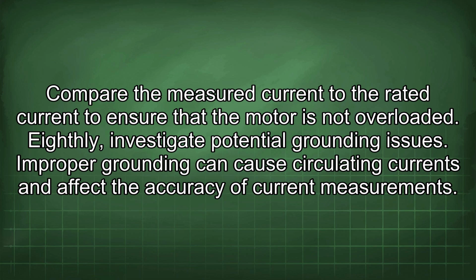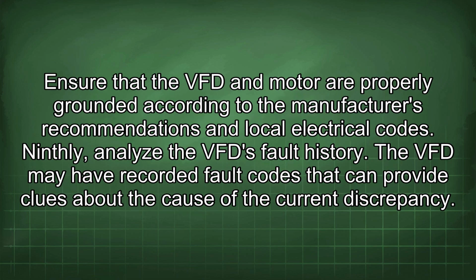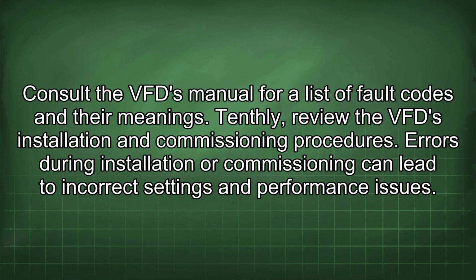Eighthly, investigate potential grounding issues. Improper grounding can cause circulating currents and affect the accuracy of current measurements. Ensure that the VFD and motor are properly grounded according to the manufacturer's recommendations and local electrical codes. Ninthly, analyze the VFD fault history. The VFD may have recorded fault codes that can provide clues about the cause of the current discrepancy. Consult the VFD manual for a list of fault codes and their meanings.